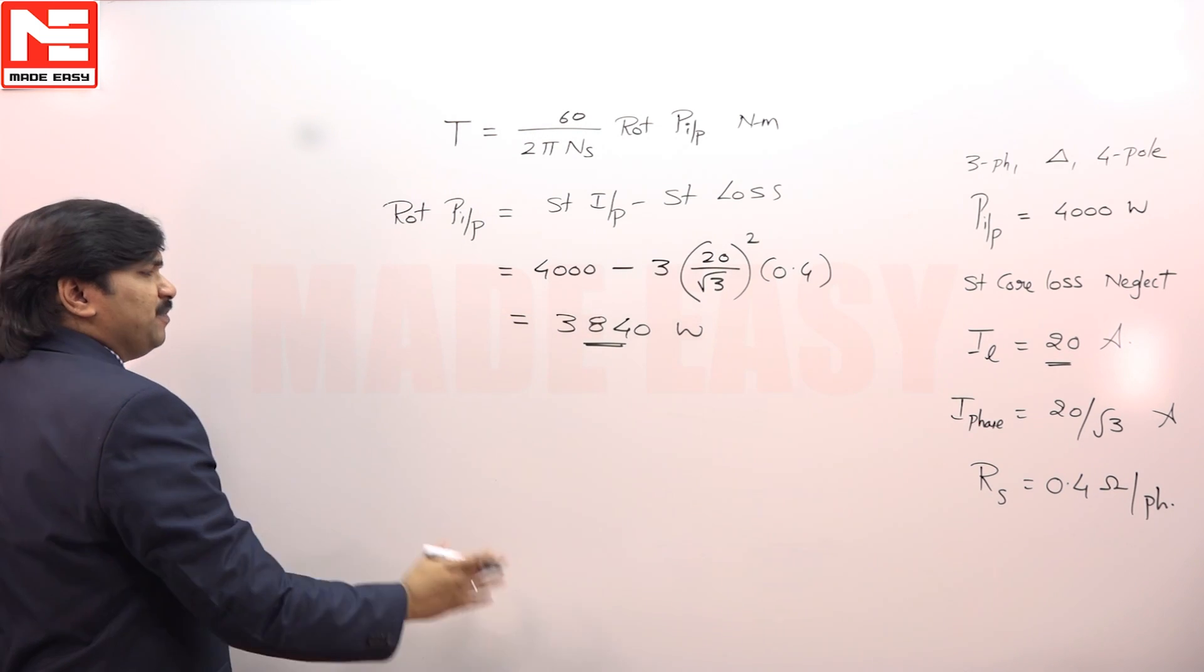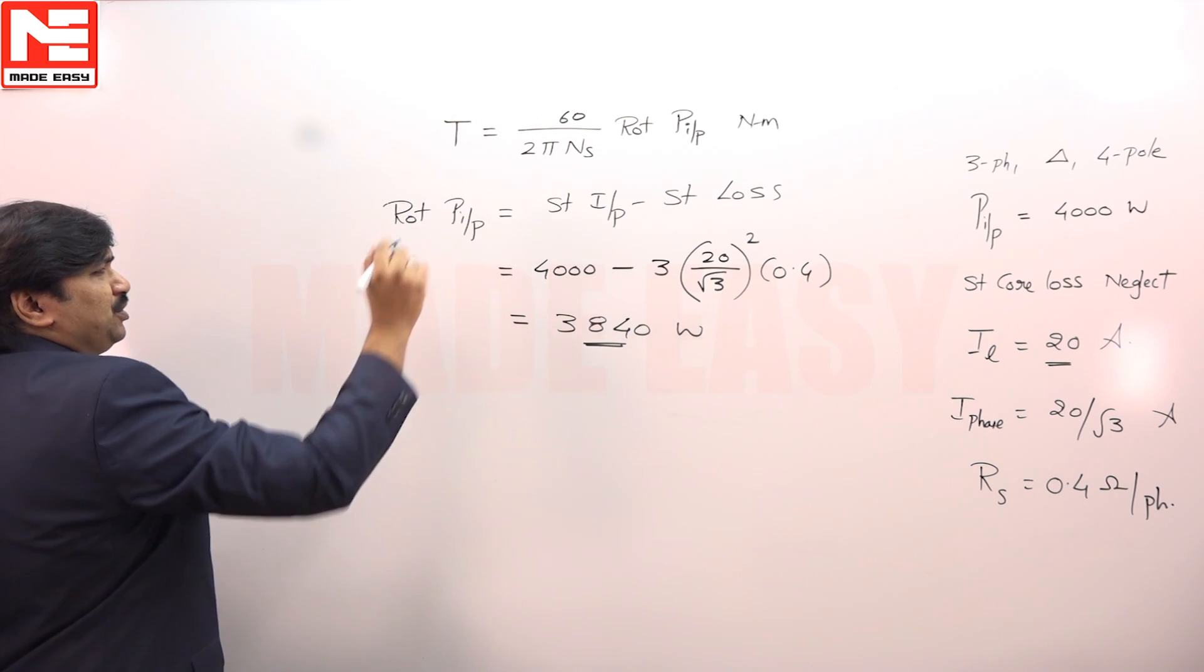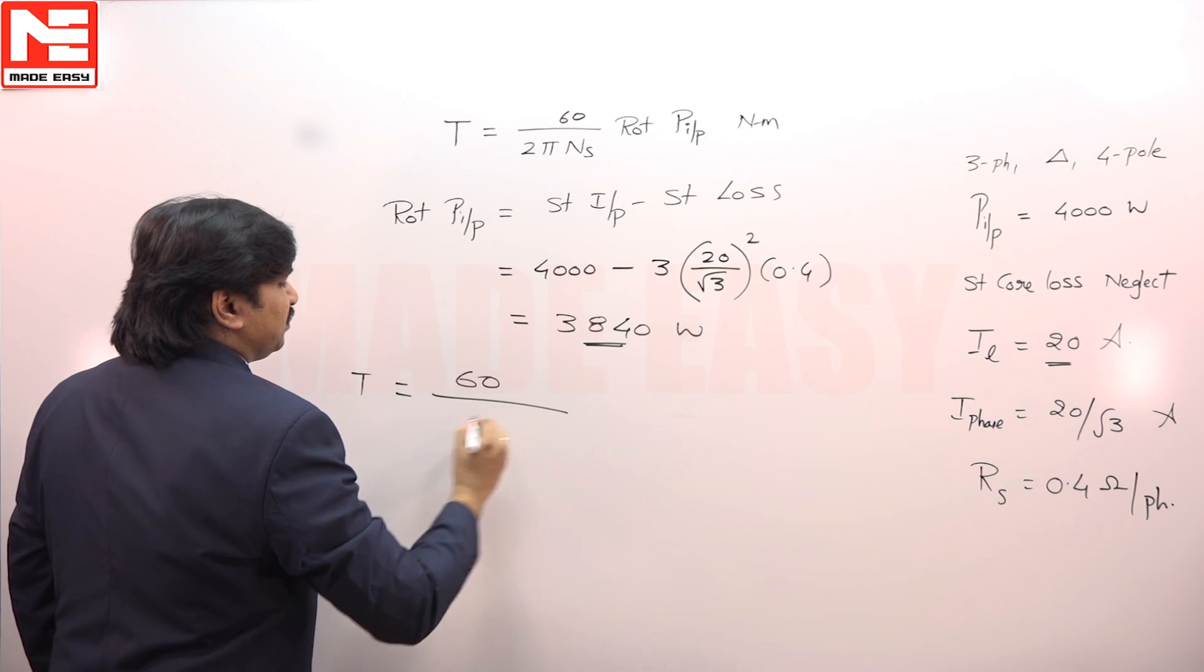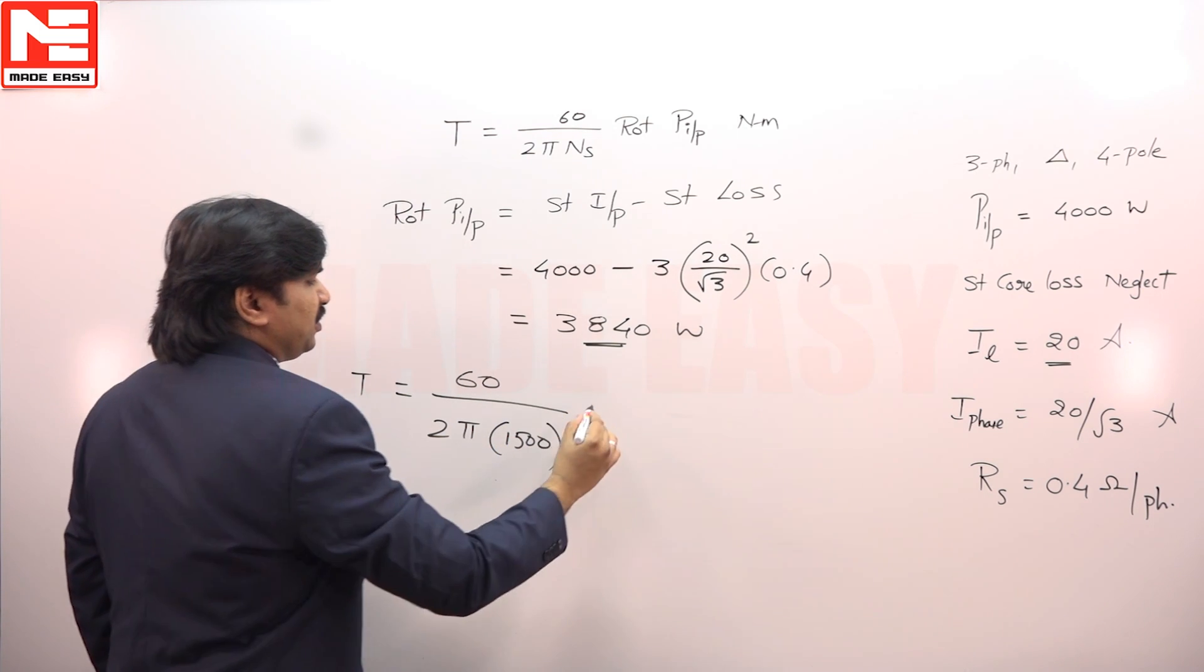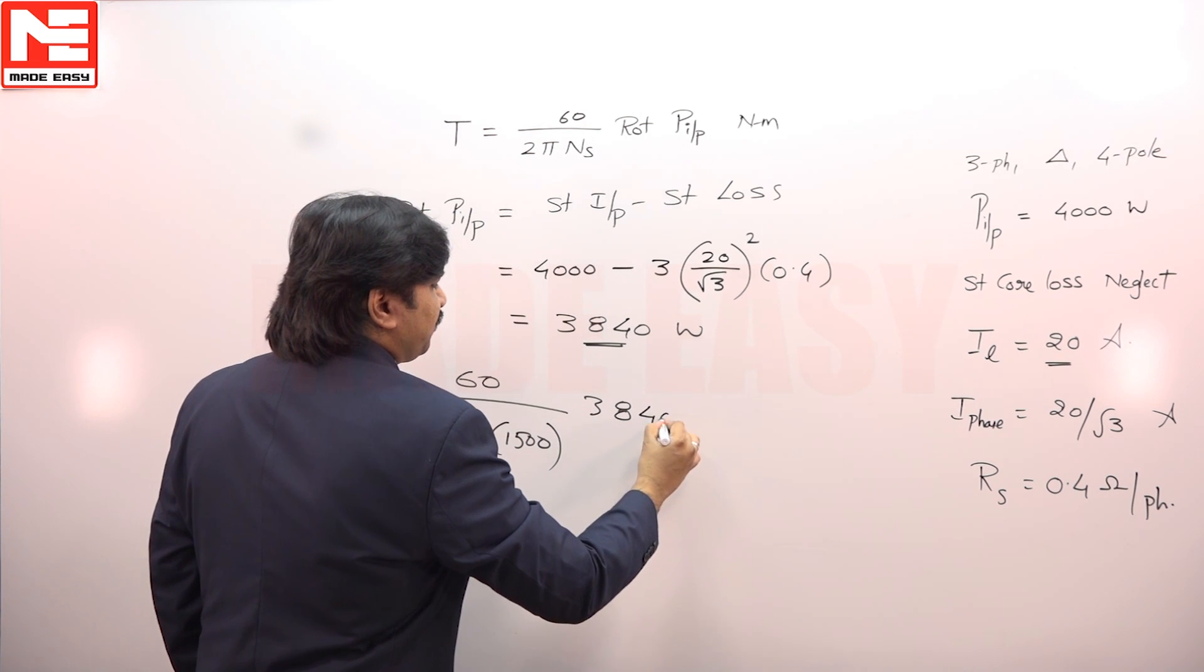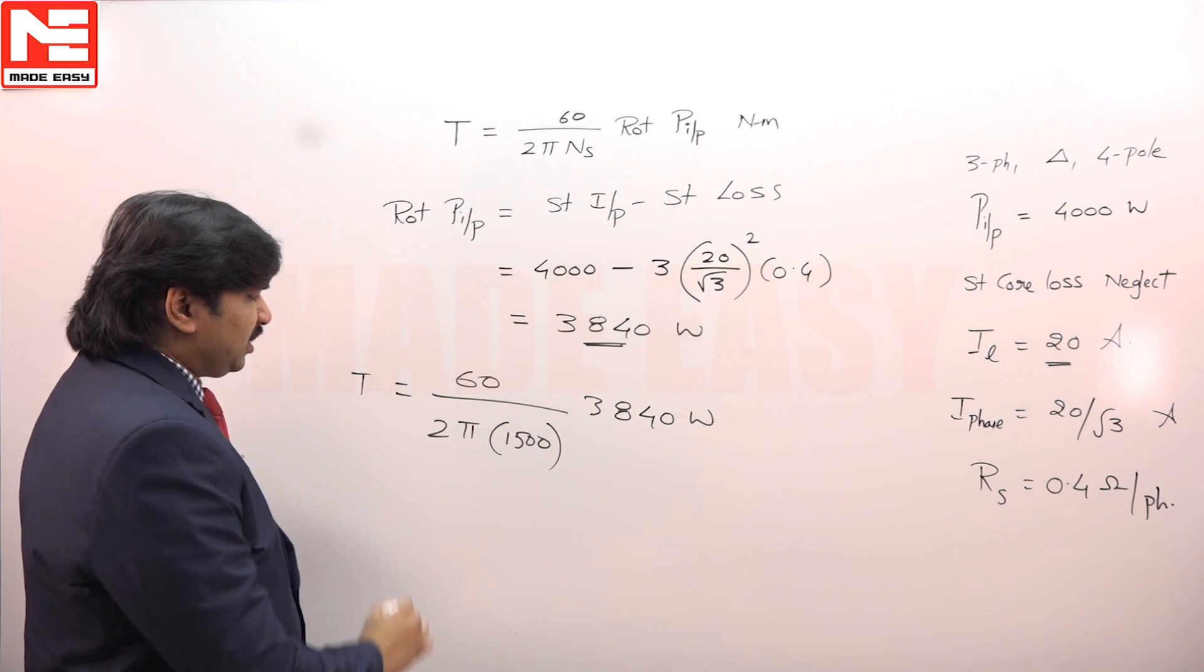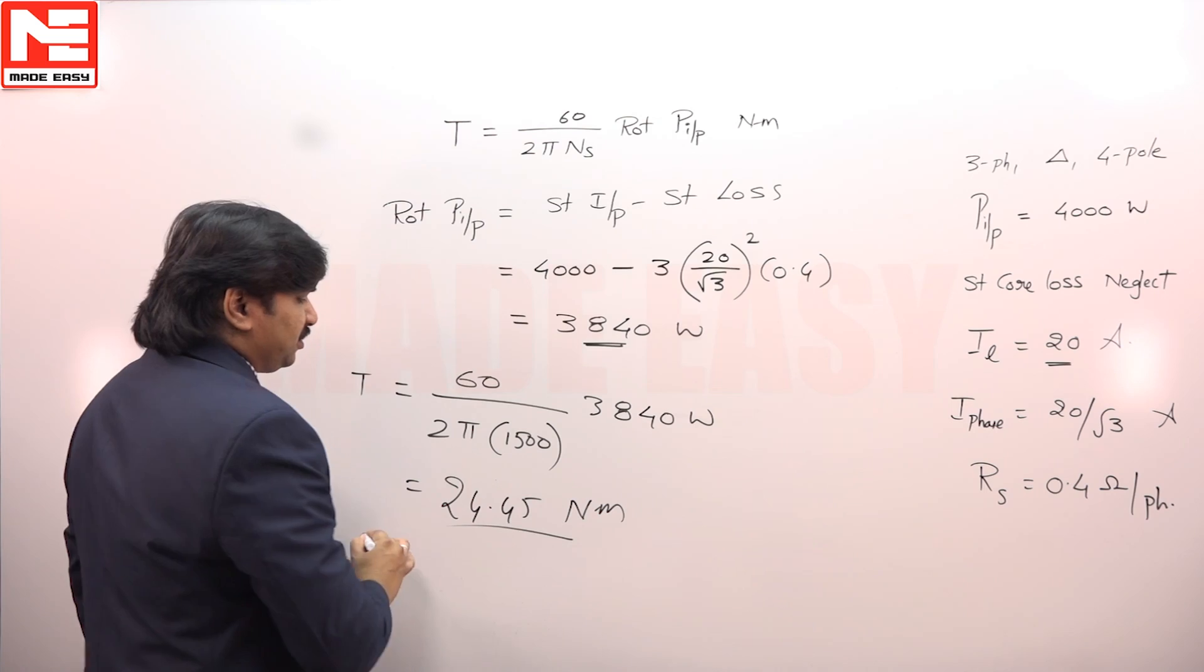Rotor input means air gap power, that is the power going on to the rotor. So we can directly substitute for torque calculation. T is equal to 60 by 2π into 1500 into 3840 watts. From this we get 24.45 newton meters.